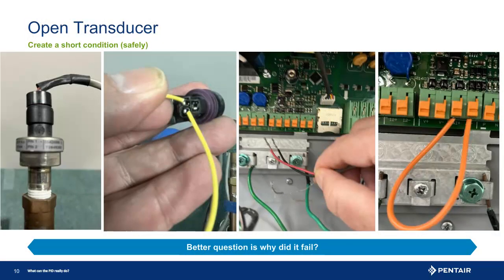Facing an open transducer, create a safe short. Note: still be cautious, this is DC milliamps, but still be safe. To start, turn off the drive and disconnect the transducer cable, and using a small gauge wire create a jumper to test the wire. Doing this, the drive once turned back on and reset, and assuming the wire is good, should read maximum PSI and then quickly fault on transducer short. If this is the case, try replacing the transducer and test run the system.